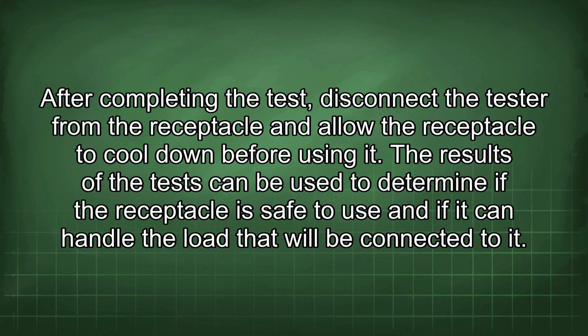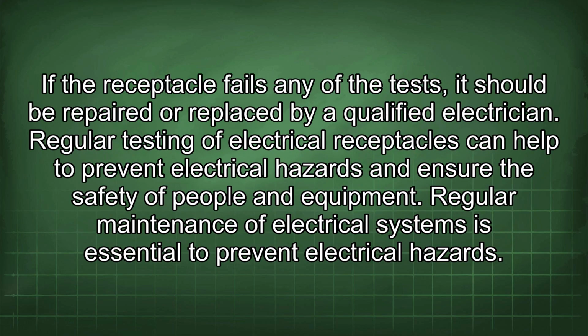After completing the test, disconnect the tester from the receptacle and allow the receptacle to cool down before using it. The results of the test can be used to determine if the receptacle is safe to use and if it can handle the load that will be connected to it. If the receptacle fails any of the tests, it should be repaired or replaced by a qualified electrician. Regular testing of electrical receptacles can help to prevent electrical hazards and ensure the safety of people and equipment.